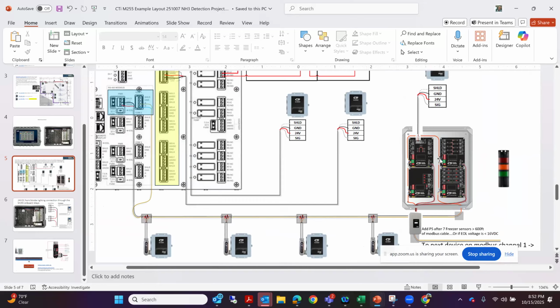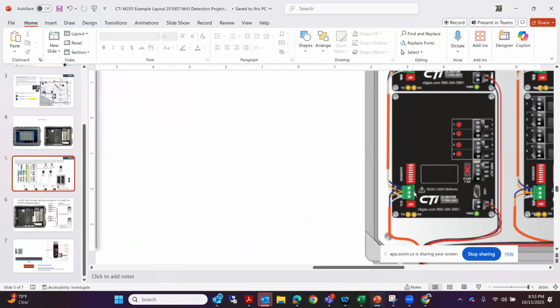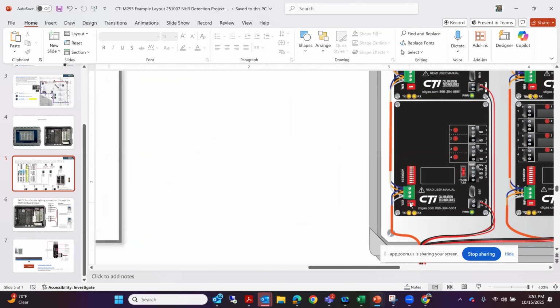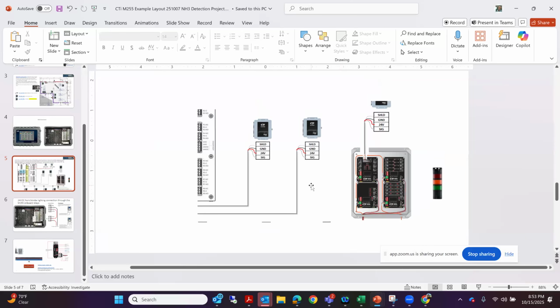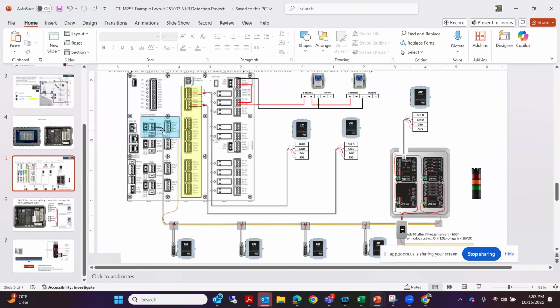It goes to this board, jumps to this board, jumps to this board, and jumps to this board. Well, this is the last one on the end of the line. There's nothing else running out here. And when it's the last one at the end of the line, there's a little EOL switch. You just throw that, and that terminates the Modbus channels on most of these Modbus systems. And that's how, when you hear EOL, that will tell you that that's an end of line device, and that should be terminated.